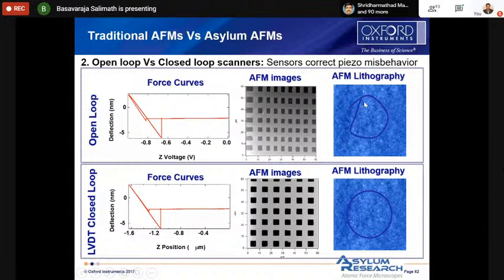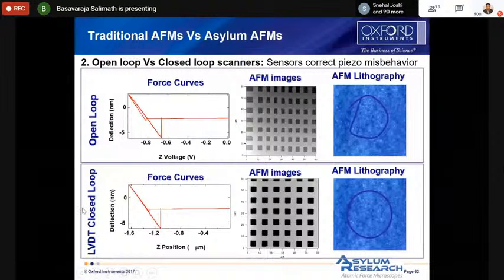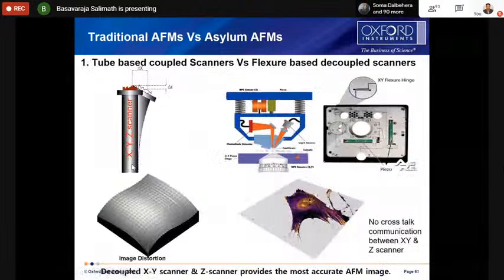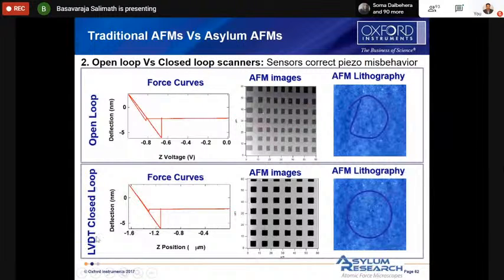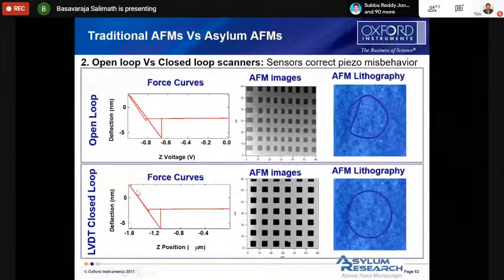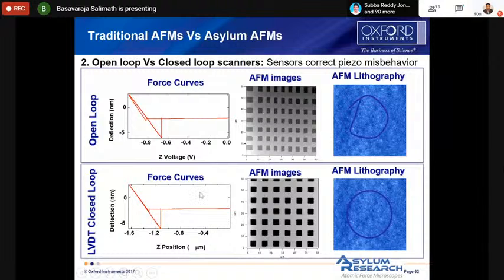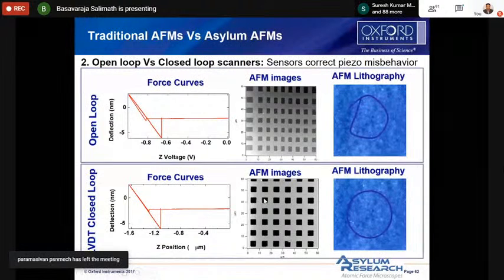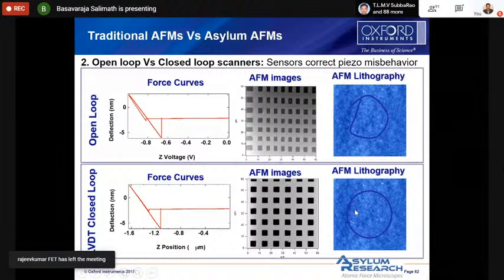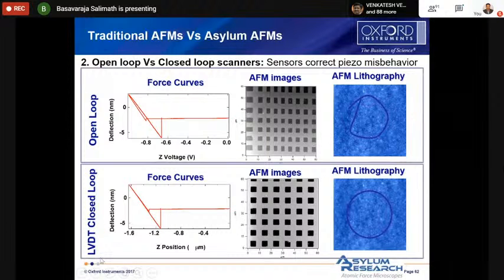Whereas in a closed loop scanner, what we do is attach an LVDT sensor to these piezo scanners. That LVDT sensor tells how much the scanner has actually moved, senses the difference, and applies extra voltage so that it comes back to the original position. Because of that, you get good force curves and very good images, at the center and at the ends also. And in lithography, if you draw a circle, you get a circle. So all our scanners are closed loop scanners.